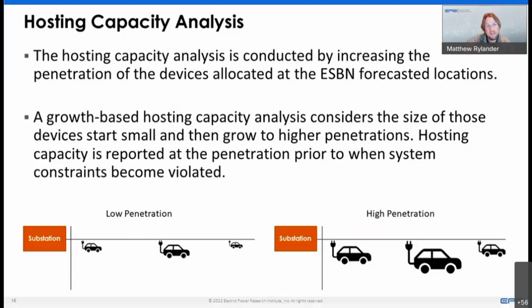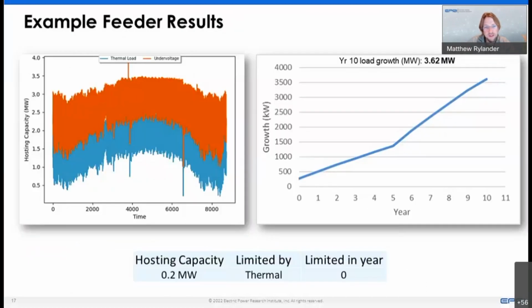It's looking at scattered growth of devices across a feeder and how much that can grow until we see a problem occur. Hosting capacity is really an evolving area of analytics where you can do it many different ways, with many different impact factors and metrics defining hosting capacity itself. But in this particular use case, we're seeing how much more load growth across an area we can accommodate before something breaks. That's really powerful for this type of study.